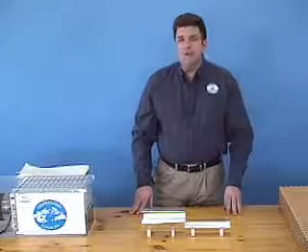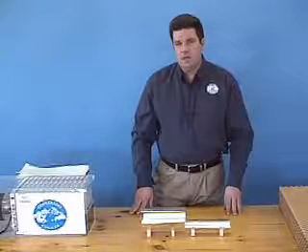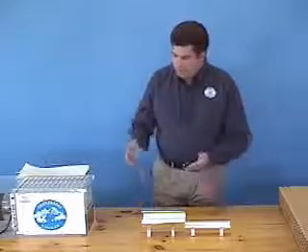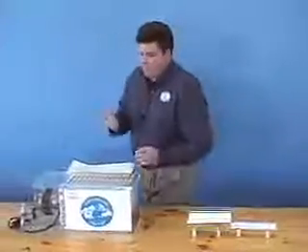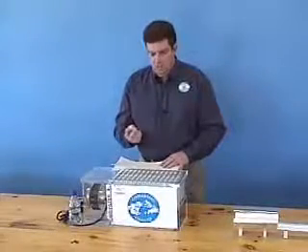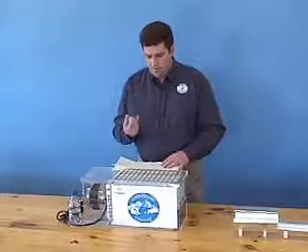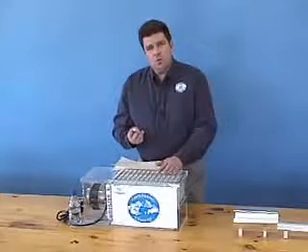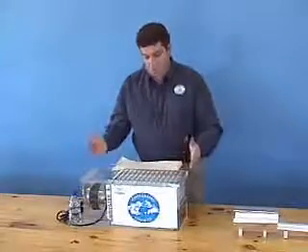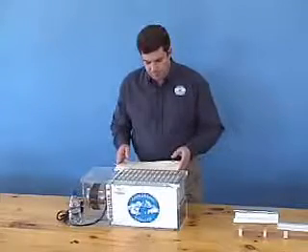In addition, you'd lose a bunch of energy to friction and pressure drop losses, so the process would be of little value. But Coolerado coolers have a small pressure drop loss, less than 1-inch column of water. We only throw away about 50% of the incoming airstream. And we can cool toward the dew point temperature of the incoming air. With this knowledge, you can begin to understand the pure genius of the Maisotsenko cycle.